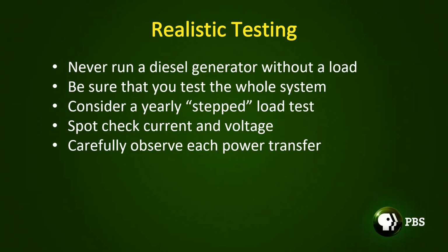So also, if you have a 3-phase transfer switch and you have a problem with one of those contacts, it may connect that phase later than the other two, which is going to cause some really undesirable cross-phase power spiking while the transfer is taking place. And you certainly don't want your recovery device to cause a failure.